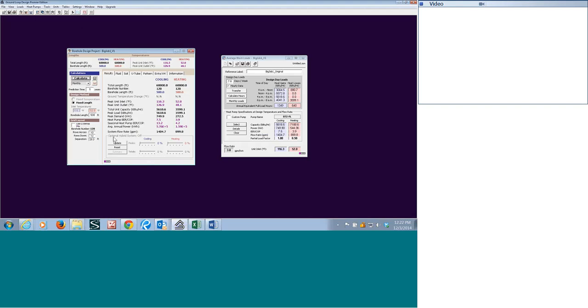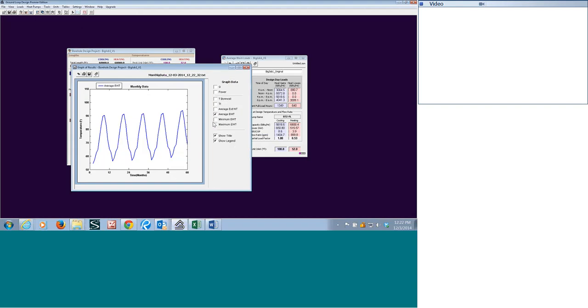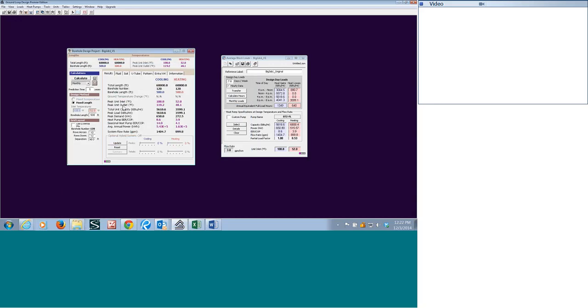But first, just to show you the impact, we're going to go back here. We had 25 foot for the 116 degrees. I'm going to take that actually to 40 foot spacing just to give you a perspective of what that could have helped with this system. That would have dropped about 8 degrees off the peak, and on a 5-year projection, you'll also notice that that slope for peaks would have really leveled off quite a bit. So it's still saying first year a little bit over 105 degrees. So that does make a difference, but let's take it back to the 25 because we can't go anywhere else with this right now. So we're back up to 116 degrees after a while.